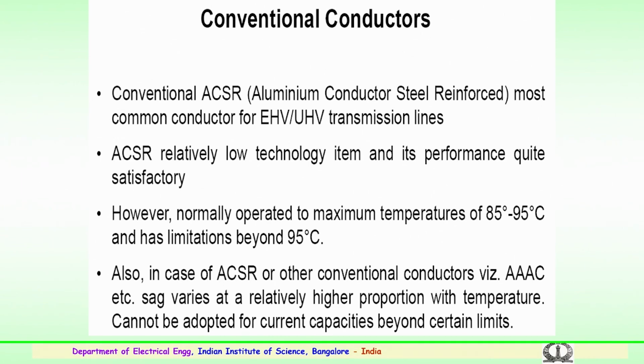However, normally when operated at a maximum temperature between 85 to 90 degrees, ACSR conductors have limitations beyond 95 degrees. If it is operated beyond that, the sag increases, and in ACSR or any other conventional conductors, it could be AAAC, all aluminum alloy conductors, the sag varies at a relatively higher proportion with temperature. So, in case the temperature exceeds 95, the sag increases at a higher proportion. So, this type of conductor cannot be adopted for operation above 90 degrees.